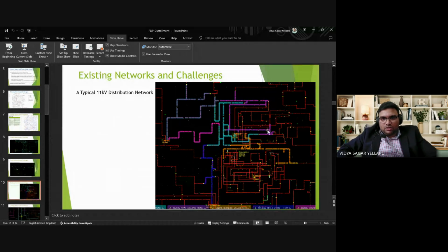It has a long bus bar, this is the bus bar, and it has many feeders connected to it. It looks like a mesh network again, but even though it looks like a mesh network, it is not a mesh network. There are some open points, normally open points, NOP. In the case of a fault here, this particular portion is isolated from the rest of the network, and the remaining parts of this circuit are given power through the neighboring feeders. So this is an open loop configuration of these radial feeders.